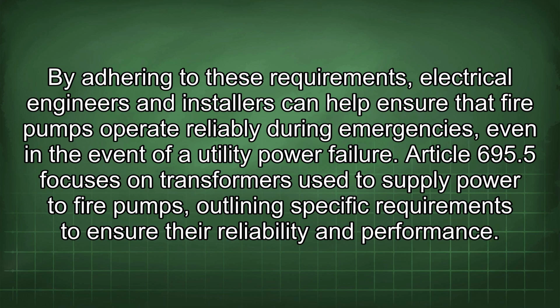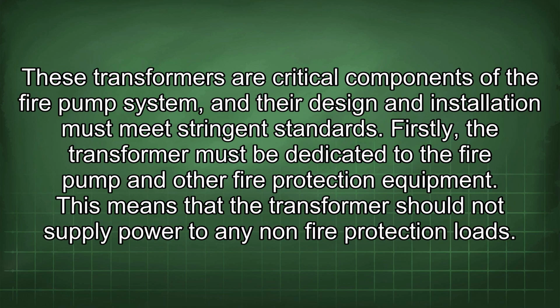Article 695.5 focuses on transformers used to supply power to fire pumps, outlining specific requirements to ensure their reliability and performance. These transformers are critical components of the fire pump system, and their design and installation must meet stringent standards. Firstly, the transformer must be dedicated to the fire pump and other fire protection equipment. This means that the transformer should not supply power to any non-fire protection loads.